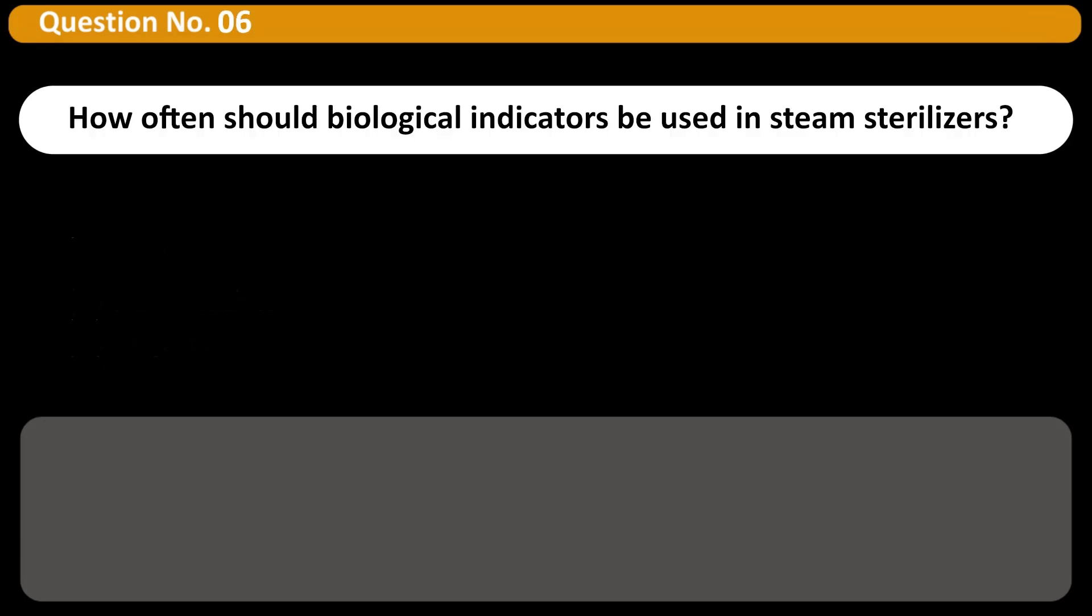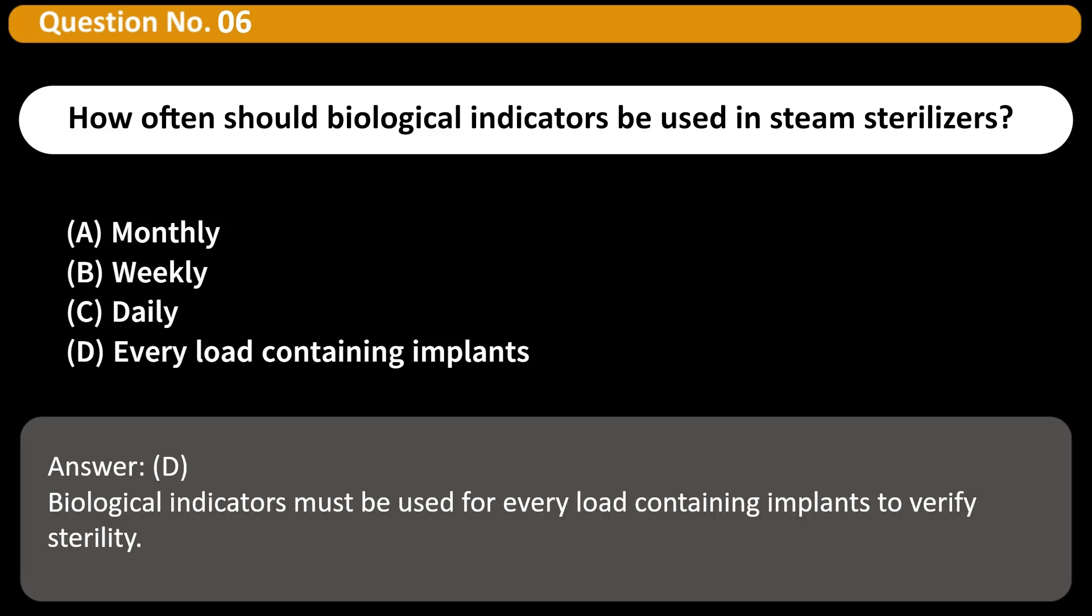How often should biological indicators be used in steam sterilizers? A. Monthly, B. Weekly, C. Daily, D. Every load containing implants. Answer D. Biological indicators must be used for every load containing implants to verify sterility.